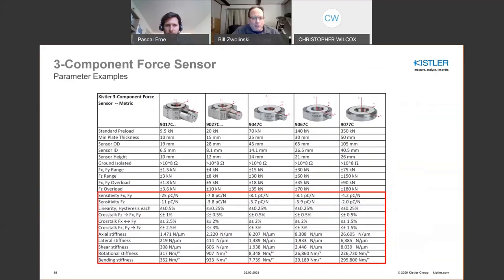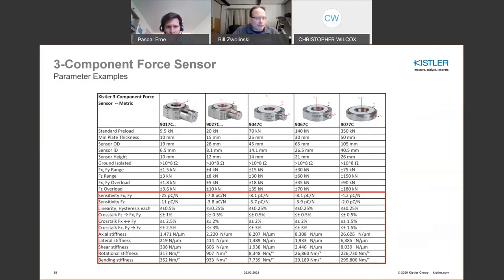Axial stiffness increases sizably as you go to higher measuring range sensors. With an external charge amp, even if your sensor is rated at 150 kilonewtons you can range it down to 1 kilonewton and still benefit from the high stiffness. There are definite reasons to look at sensors in terms of stiffness, the number of sensors, and geometry of your force plate to achieve your performance goals.